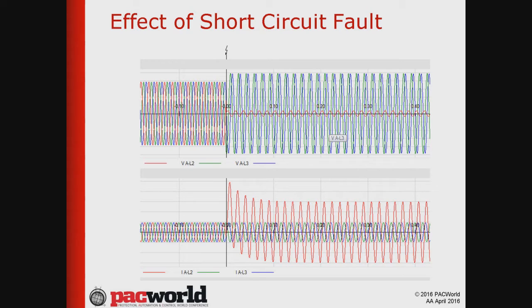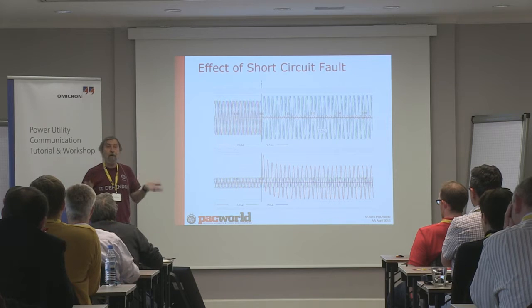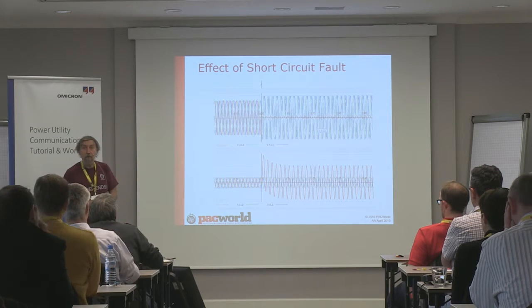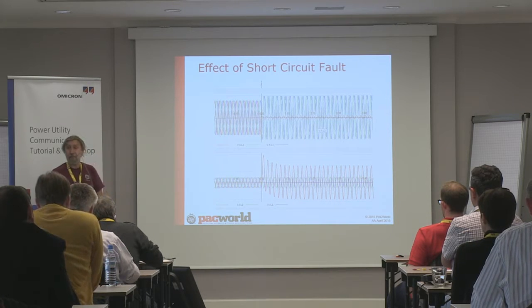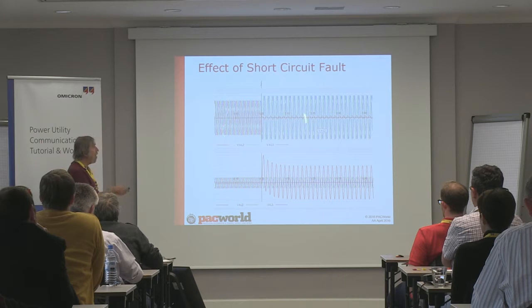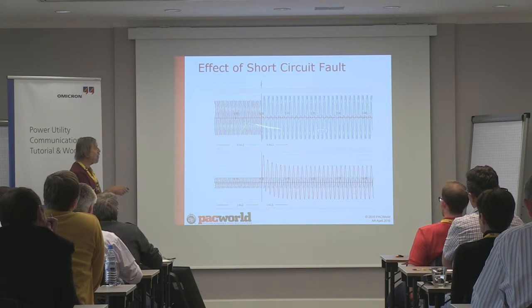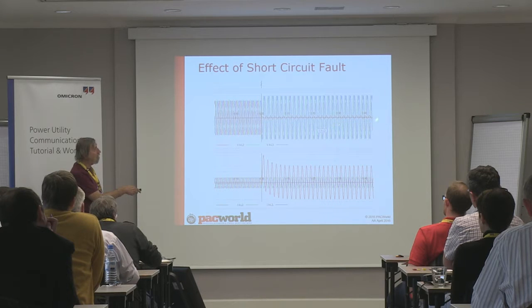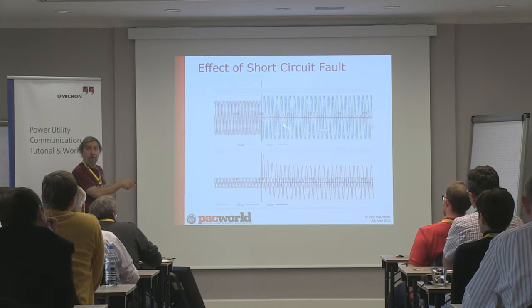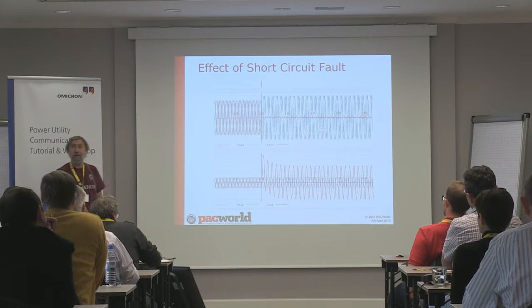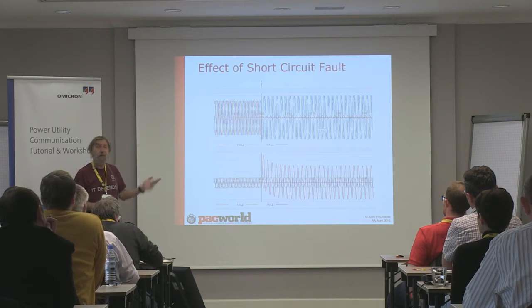Another issue is what we are seeing now in many, many countries, especially in Germany. When you fly over Germany or when you drive on the freeways or on the roads in Germany, you see this huge amount of wind generators. The problem with wind generators is they're sensitive. There is something that is called a voltage sag, okay? So what you see here is a single phase to ground fault, and when you have a single phase to ground fault, you see here in the faulted phase, I have a very significant voltage sag. The problem with the wind generators is that they may not be able to withstand this voltage sag.